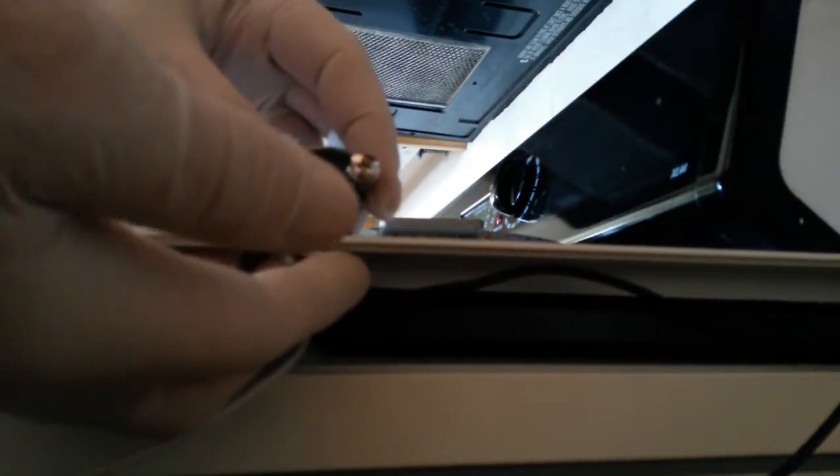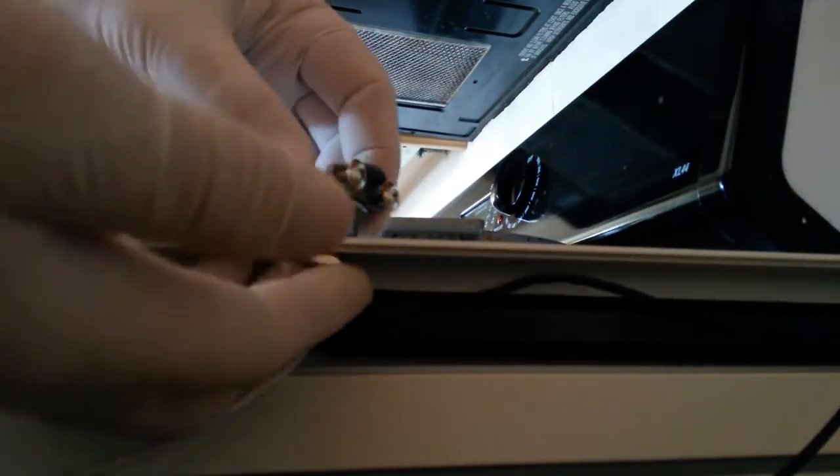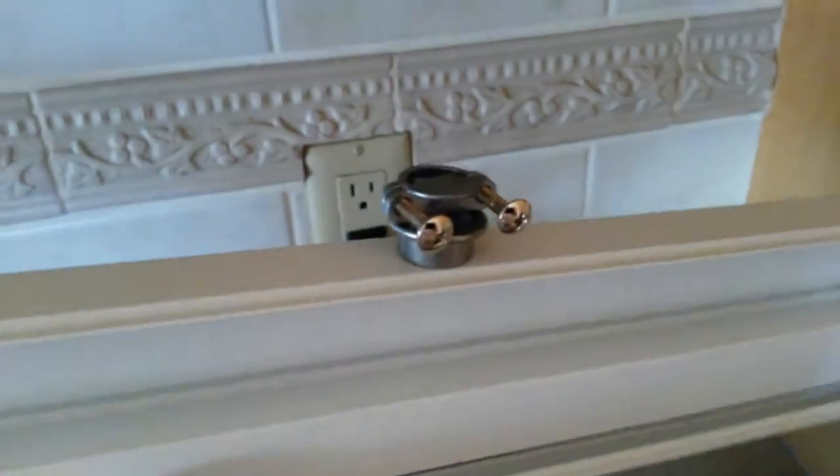Now we're going to put in the BX adapter. I'm going to assemble it because it has the compression clamp on it. It's much easier to assemble that right now than to try to do it on the actual frame. And I'm going to drive in the screws deep enough so that it holds everything. Put the nut underneath. Make sure that your screw heads end up facing towards the lights. Okay, the BX adapter is on.